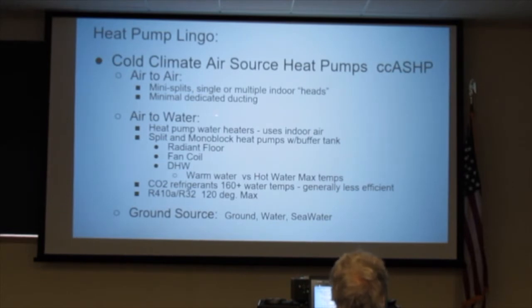I also want to talk a little about air to water, because that's what I've been playing with a bunch as well. Basically it's the same outdoor unit, only instead of running this warm refrigerant up to that little fan coil on the wall, it's running it through a little flat plate heat exchanger that's taking cold water out of the bottom of my storage tank, taking heat out of that refrigerant and putting it into my tank. So I'm making warm water—not hot water, but warm water.